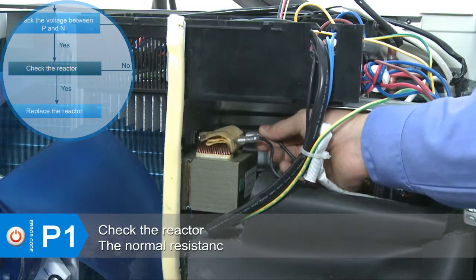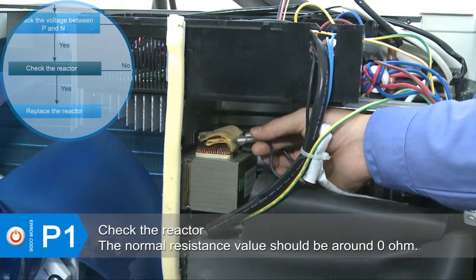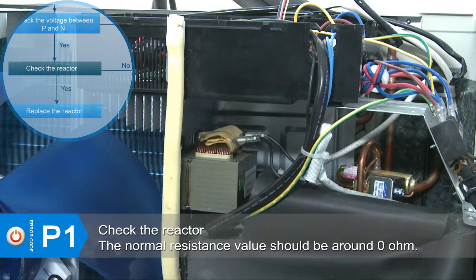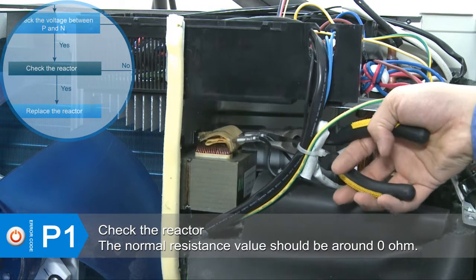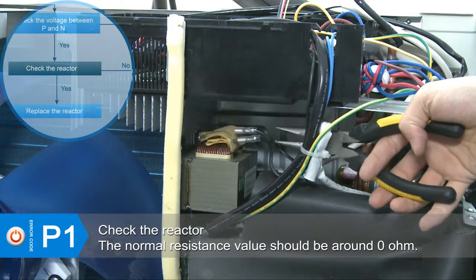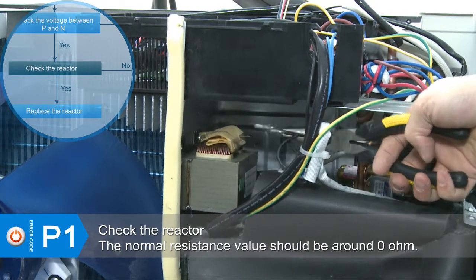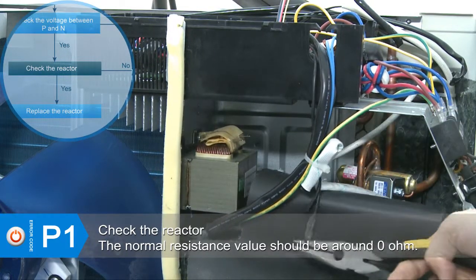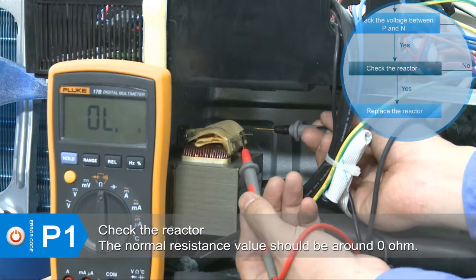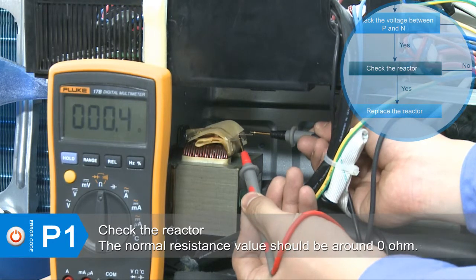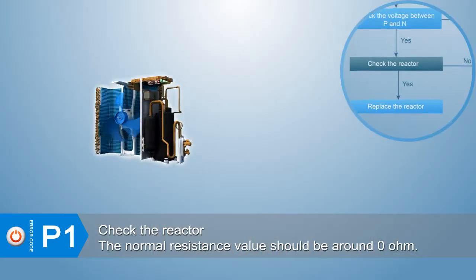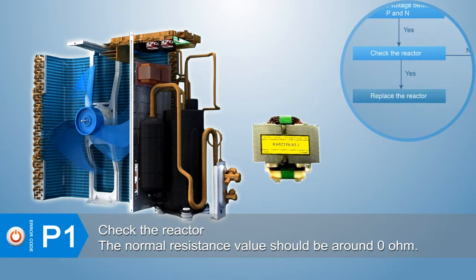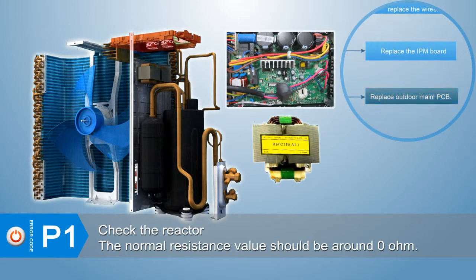After the maintenance above, there could be two cases. If the voltage is normal, check the wiring of the reactor. If the wire is well connected, measure the resistance value of the reactor. The normal resistance value should be around 0 ohms. If not, replace with a new reactor. If the error still exists, replace the outdoor main board.